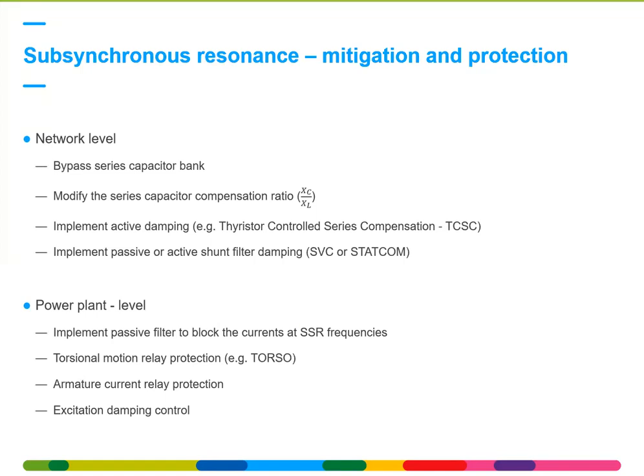Mitigation and protection is, of course, possible, but again, it should be done for every grid configuration. So it can be done on the network level or on the power plant level. On the network level, the most straightforward one is to bypass the series capacitor bank, which is causing the interaction. You can implement also active damping, passive damping. So different examples or solutions exist.